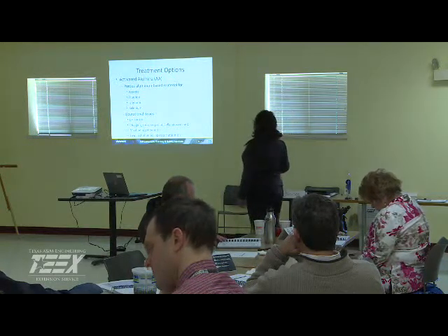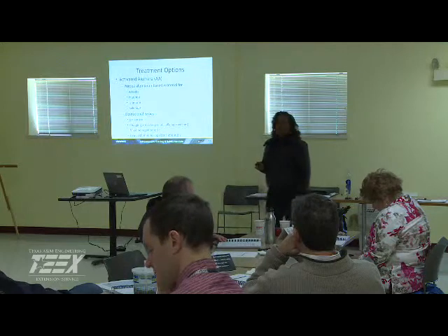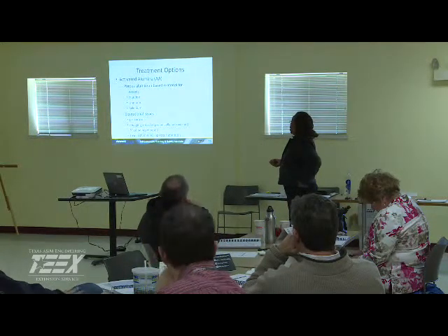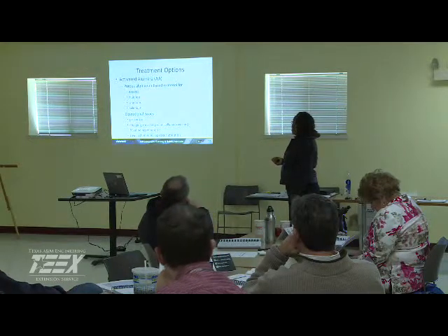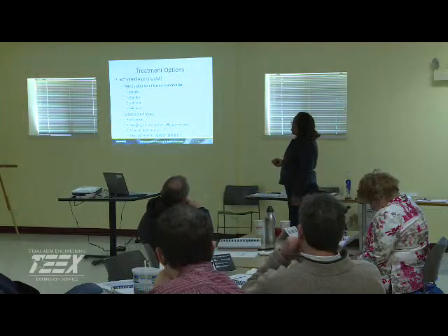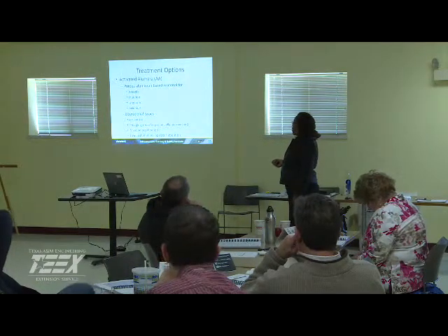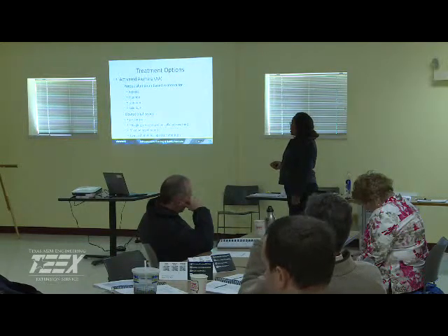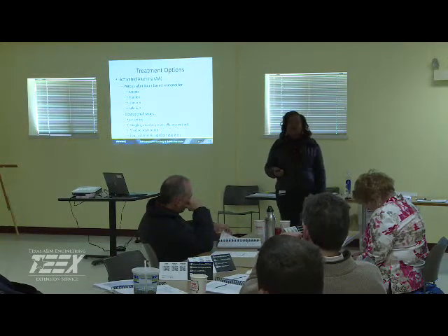All right, we'll just go in a nutshell over what each of the different treatment options entails. With your activated alumina beds, it's a porous aluminum-based material and they're good for arsenic removal, fluoride, uranium, as well as selenium. But the operational issue with activated alumina is that it's pH dependent.